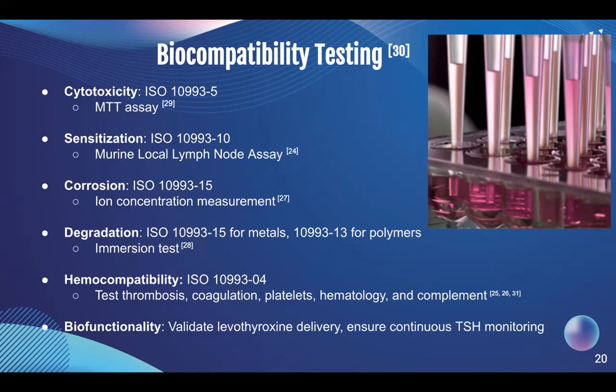Degradation tests are quantitative and are necessary for new medical devices. This information must be presented for any medical device that has potential for degradation in the human body, and that's according to the ISO standard. An in vitro test will be performed to determine the rates of degradation and the release of any toxins of our device.